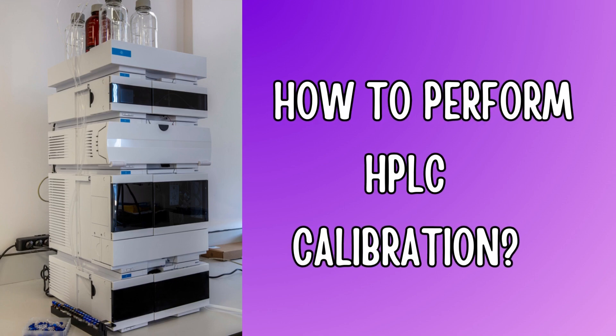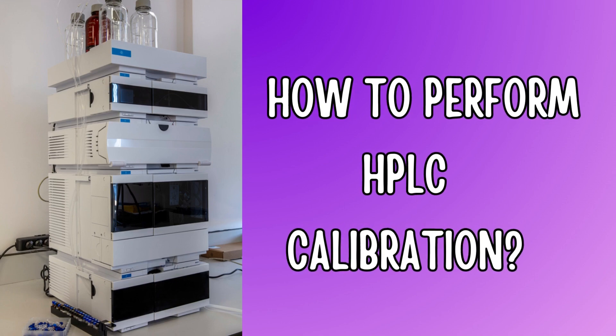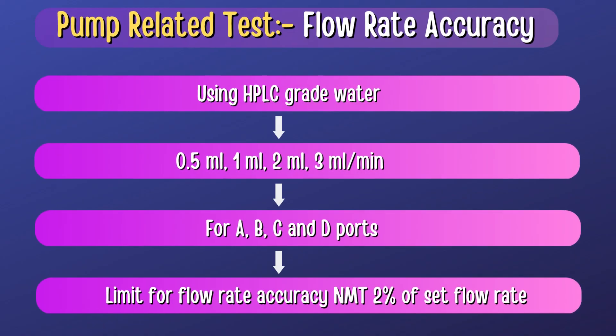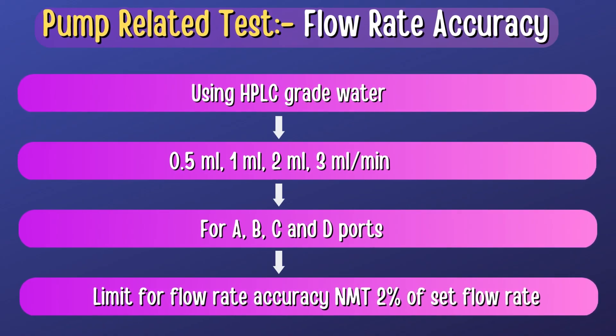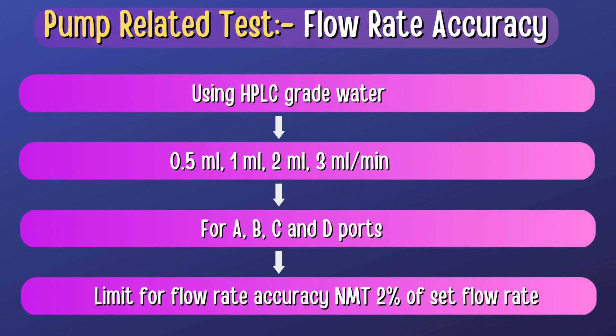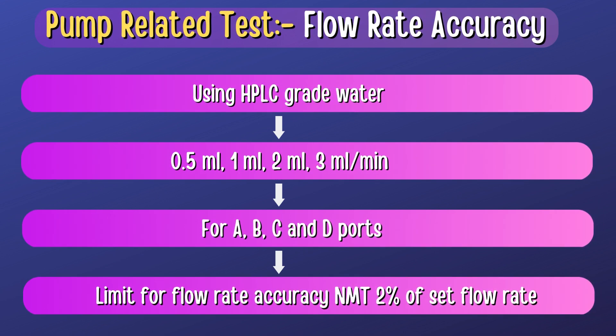Now we will understand how to perform HPLC calibration along with its limits. Flowrate Accuracy and Precision is performed using HPLC grade water, with measurements taken at different flow rates such as 0.5 ml, 1 ml, 2 ml, and 3 ml per minute for all ports A, B, C, and D. The limit for flow rate accuracy should not be more than 2% of the set flow rate.